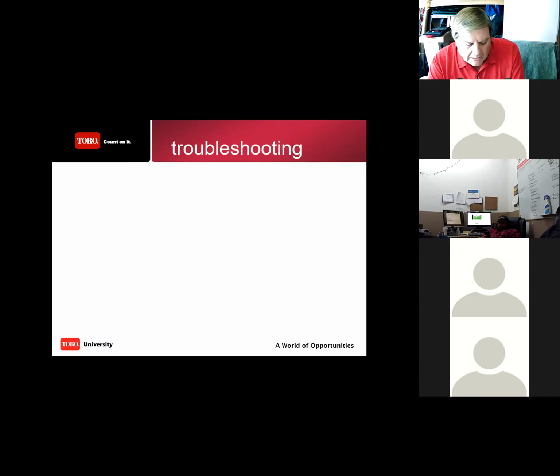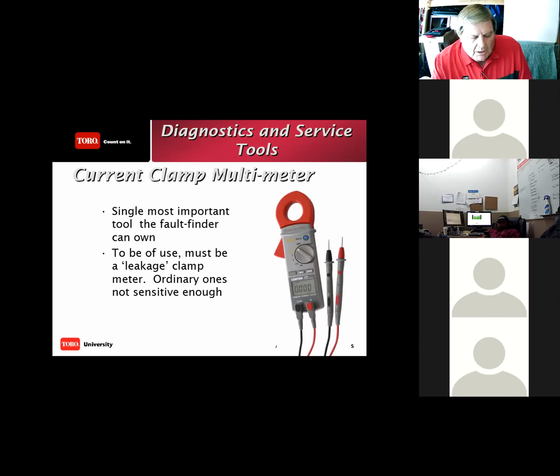All right. Let's get into the fun part, probably what a lot of you folks are here to listen for. Not just the design aspects, not just the unique pieces of 2-wire, but let's talk about troubleshooting, because this is going to be a big part of our lives moving forward. So, as mentioned previously, different brands have different brand test devices, but those test devices are brand specific. You must use the test device for Hunter devices, Toro for Toro devices, Ringmaster for Ringmaster devices, and so on and so forth. If you want one test device that works with every manufactured 2-wire system, that would be what we call a clamp meter.